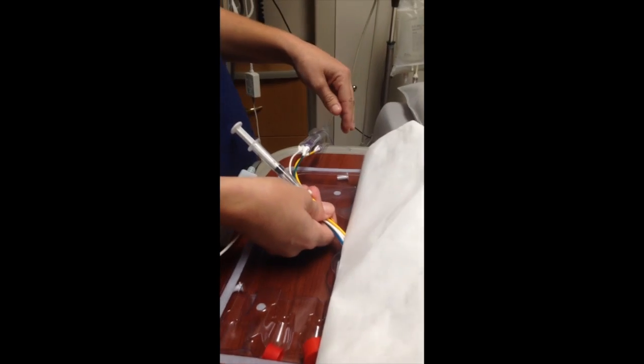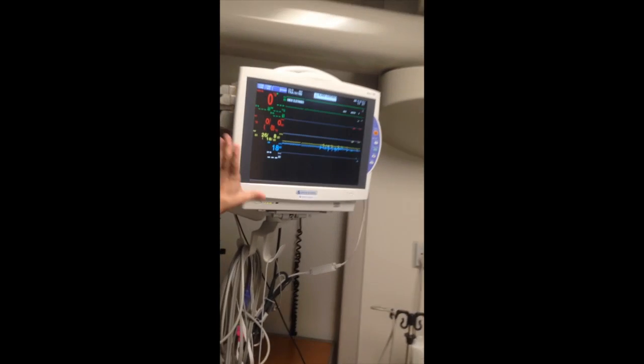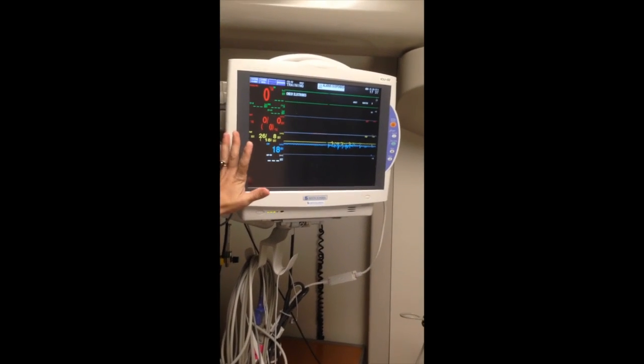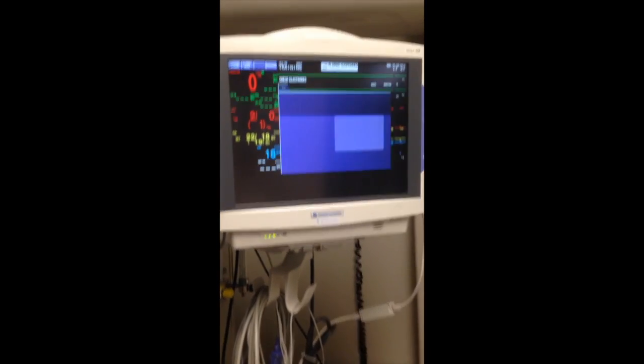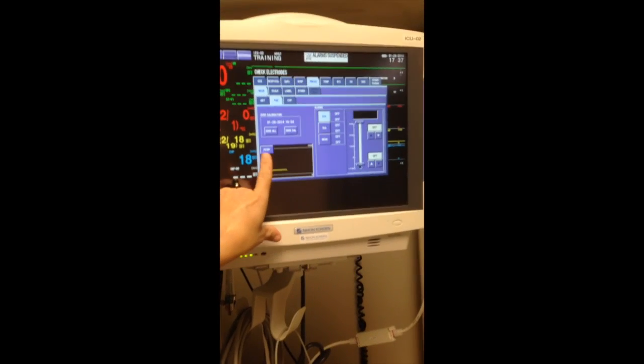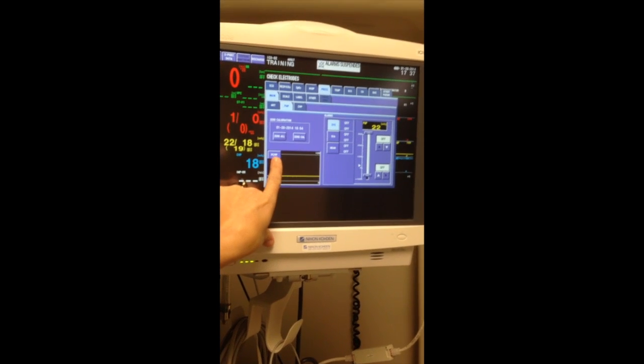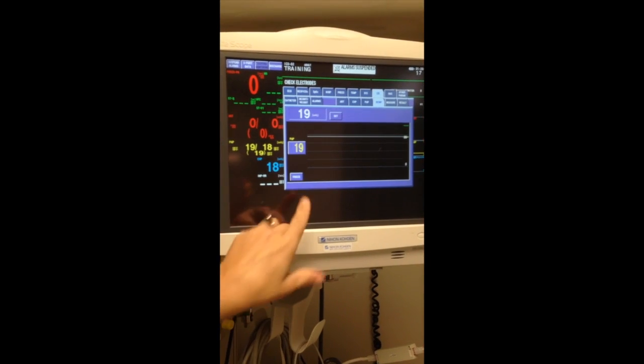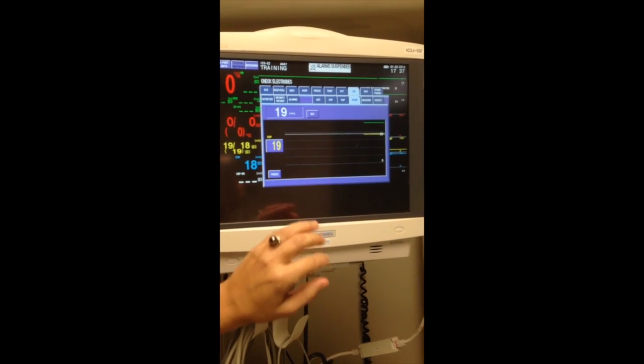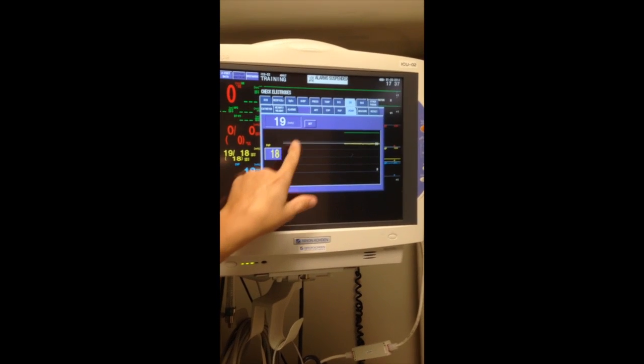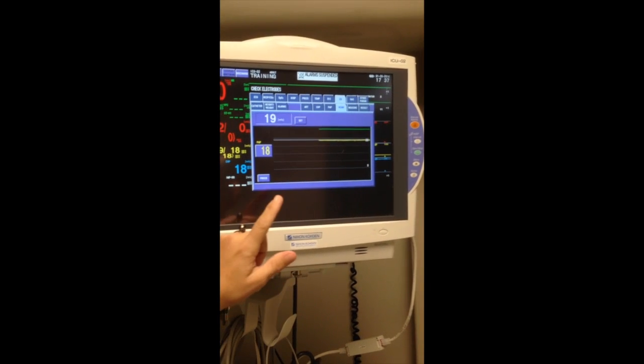The other important part about when you're setting this up for the physician is that you want to make sure the monitor is set up in the wedge screen. So to do that, you push your PA line, and then on here there's a wedge button. You push the wedge button and it comes up to this screen. This way they are able to see the Swan floating in and see the waveforms.